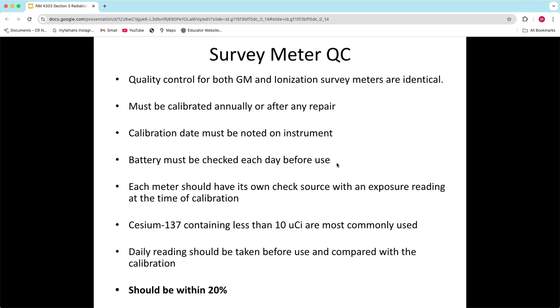But it'll be attached to the side of the meter. At some facilities, you could have them not attached to your meter. If so, they would be in the hot lab, I'm assuming, somewhere. And usually they're labeled so that you know which source goes with which meter, because they're specific. So you won't have one source that just works for all your meters. It should be a source with every meter that you have. And so if they are separated, make sure you're measuring the right QC source every day to get a reading. And then again, if it's connected, that makes it a little bit easier. But that daily reading should be taken and compared to the calibration.